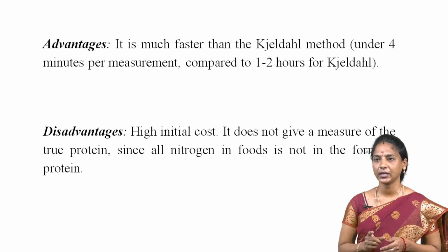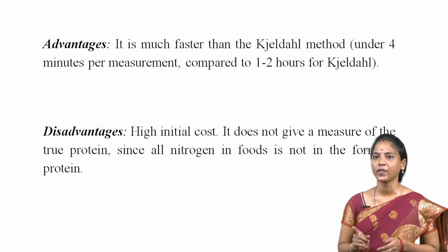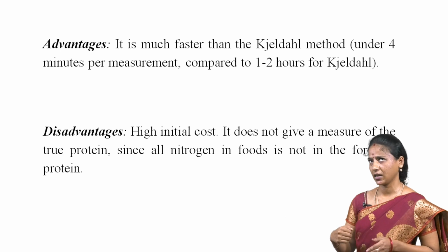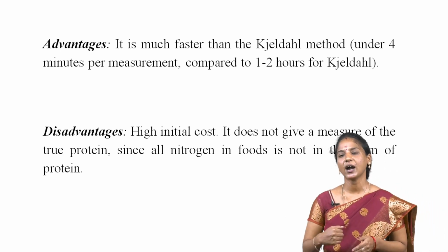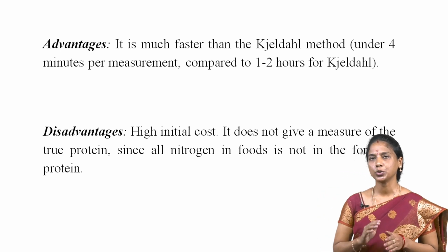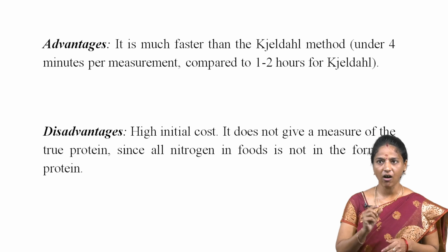Advantages: it is much faster than the Kjeldahl method, under 4 minutes per measurement compared to 1 to 2 hours for the Kjeldahl. It does not need toxic chemicals or catalysts. Many samples can be measured automatically. It is easy to use. The disadvantages: a high initial cost.